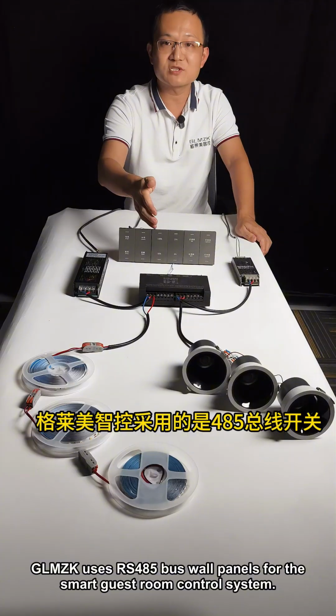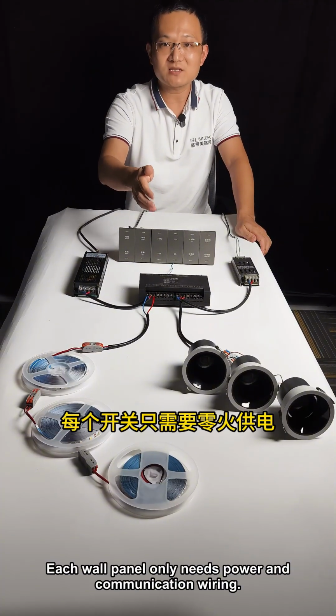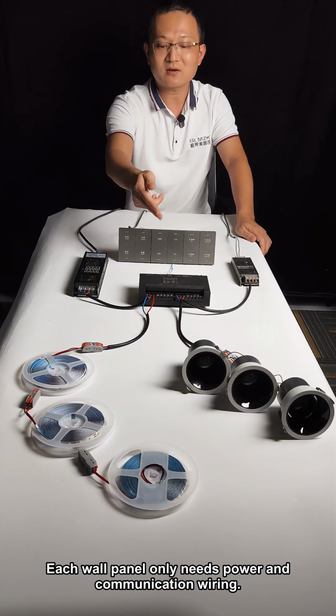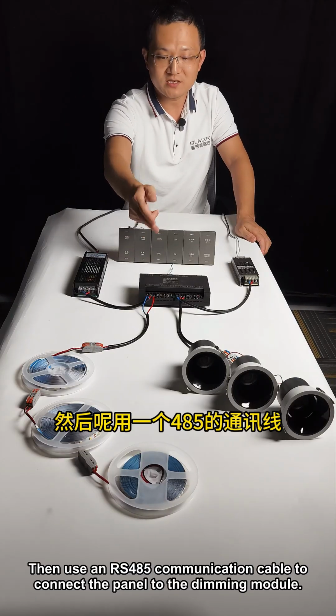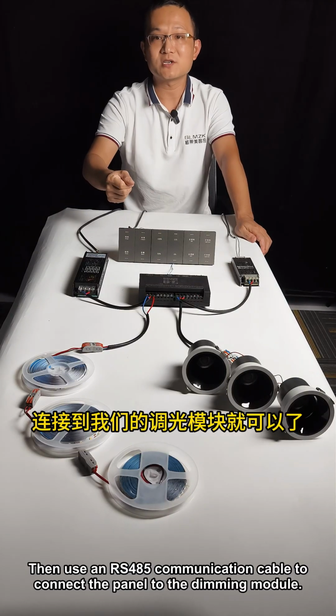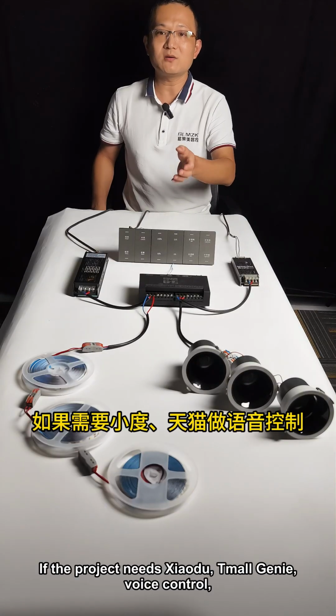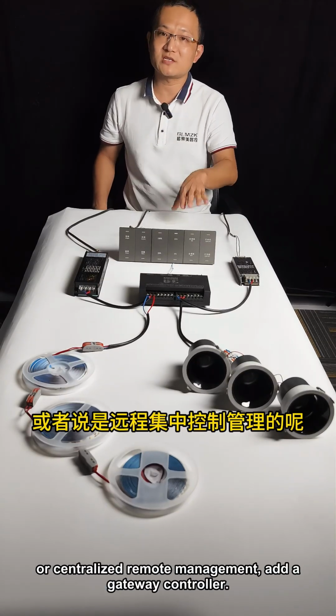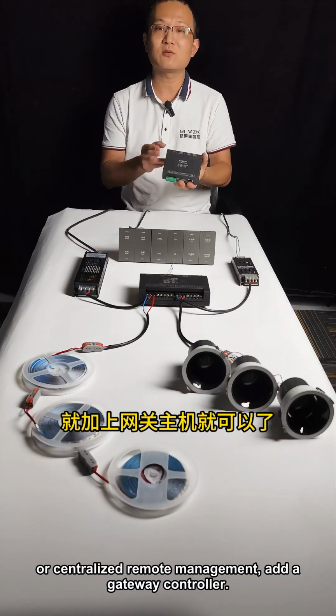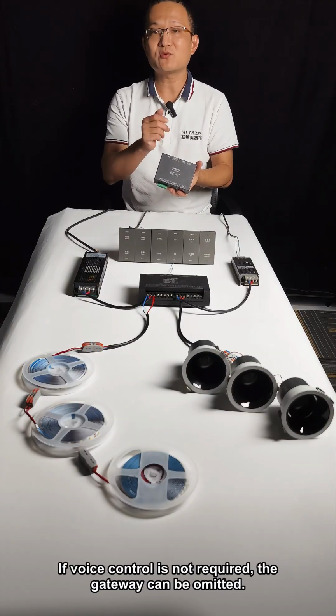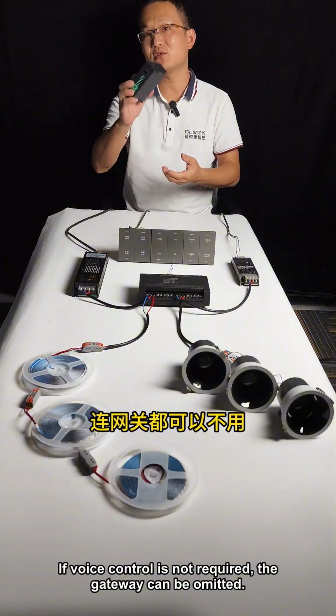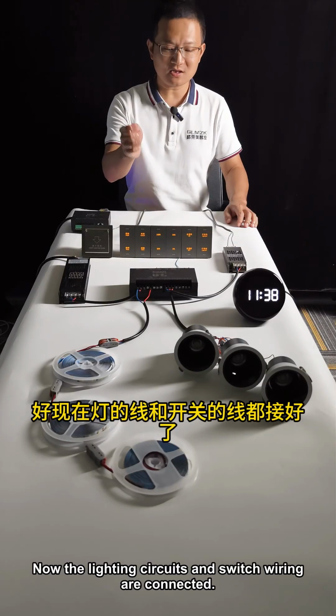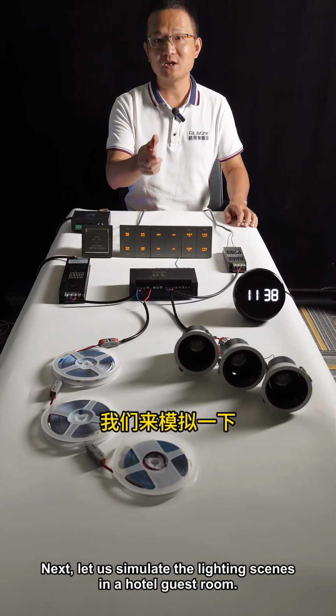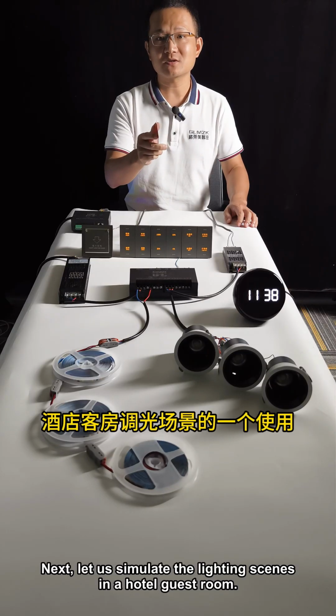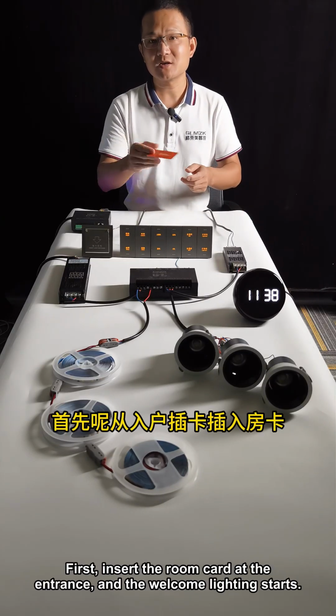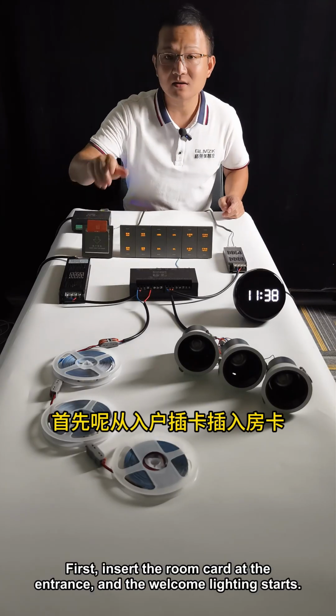Next question, how do we connect the wall switches? GLMZK uses RS485 bus wall panels for the SmartGuestRoom control system. Each wall panel only needs power and communication wiring. Then use an RS485 communication cable to connect the panel to the dimming module. If the project needs Alexa, Tmall Genie, voice control, or centralized remote management, add a gateway controller. If voice control is not required, the gateway can be omitted. Now the lighting circuits and switch wiring are connected.